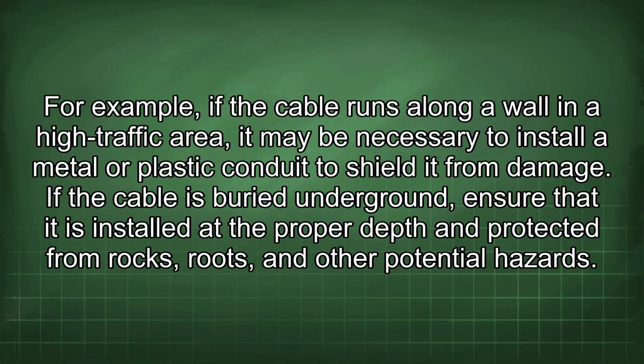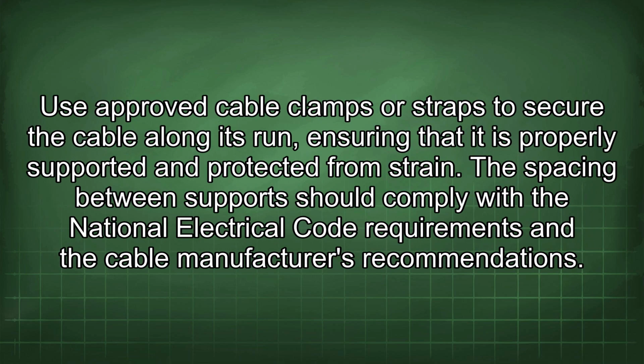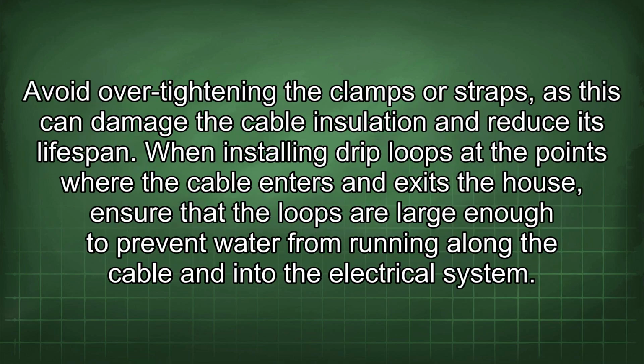If the cable is buried underground, ensure that it is installed at the proper depth and protected from rocks, roots, and other potential hazards. Use approved cable clamps or straps to secure the cable along its run, ensuring that it is properly supported and protected from strain. The spacing between supports should comply with the National Electrical Code requirements and the cable manufacturer's recommendations. Avoid over-tightening the clamps or straps, as this can damage the cable insulation and reduce its lifespan.